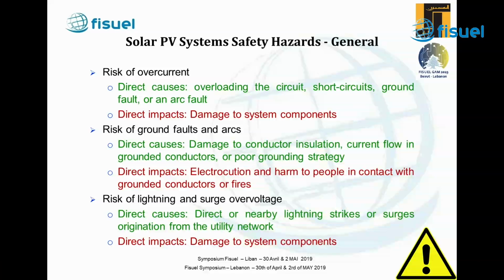We have the risk of ground faults and arcs, which is caused by damage to the conductor insulation itself and current flow in grounded conductors. The direct impacts will be high risk of electrocution for anyone in direct contact with grounded metal conductors, and also one of the highest causes of fires in solar PV systems. The third main risk is the risk of lightning and surge overvoltage caused by direct or indirect effects of lightning, and sometimes surges originating from the utility network itself. Also, the impacts are damage to system components and possibly fires.